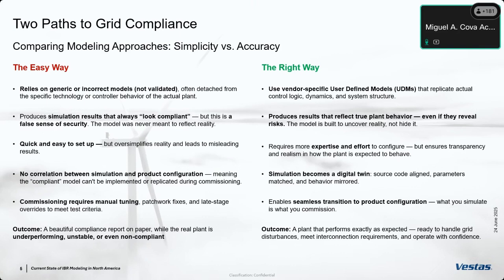Following the easy way will sometimes require manual tuning and patches just to pass the commissioning, zooming in a lot on the couple of tests we're doing in mock testing. But that doesn't mean the plant will actually represent the exact same performance when facing LVRTs, HVRTs, or any other kind of disturbance in the grid.